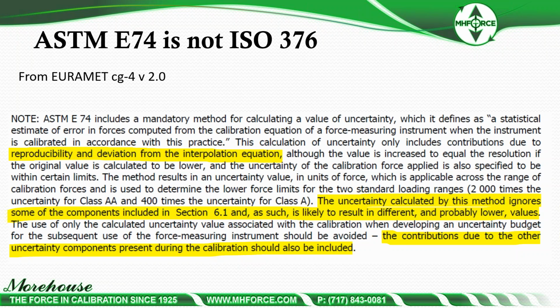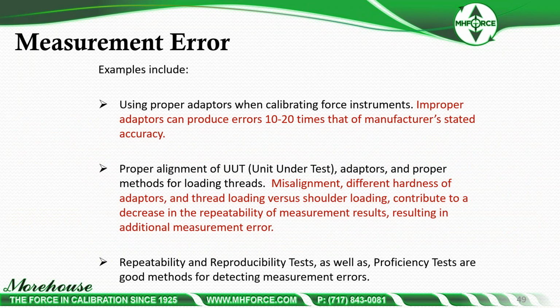So when you get a cal with ASTM E74, by rights, you have a little more work to do to quantify all the additional error sources. And then ISO addresses adapters, and using proper adapters when calibrating force instruments. Improper adapters can produce errors 10 to 20 times that of manufacturer stated accuracy.